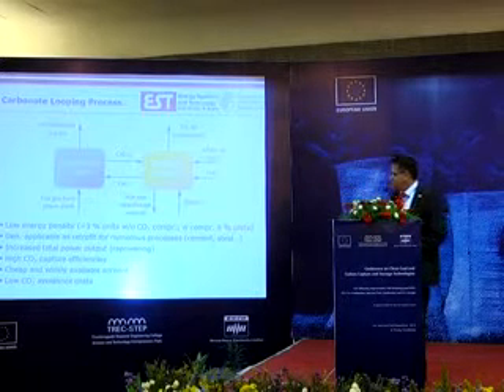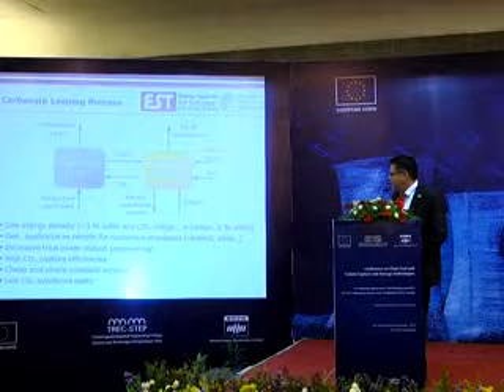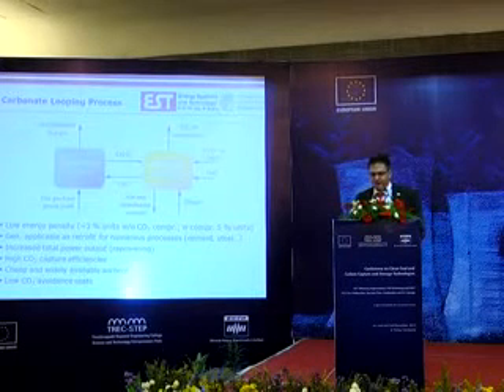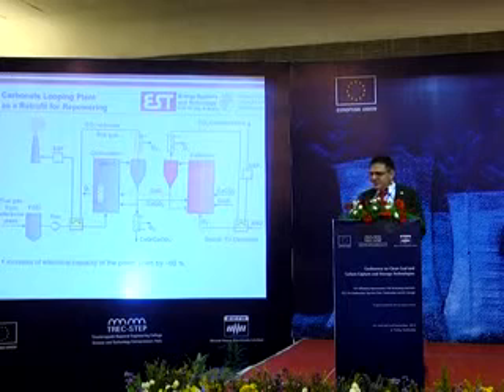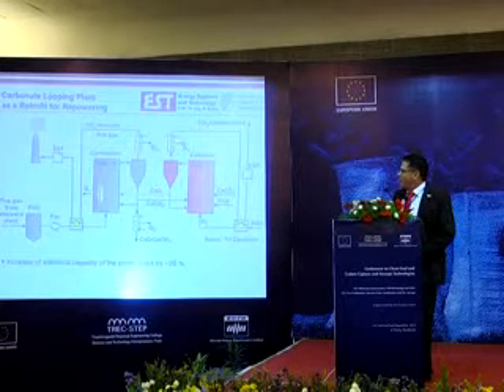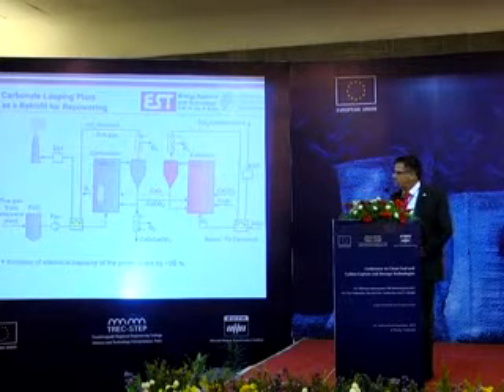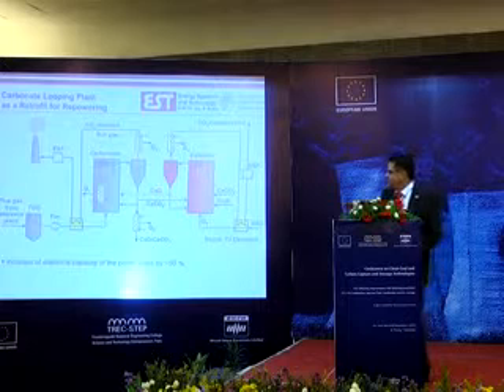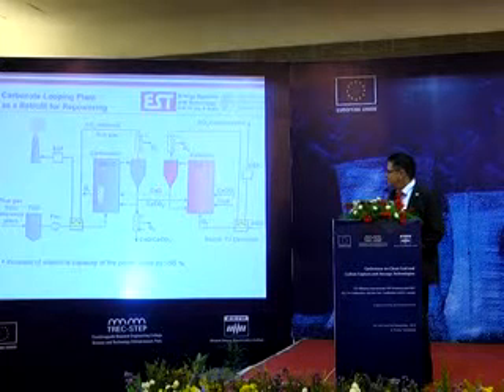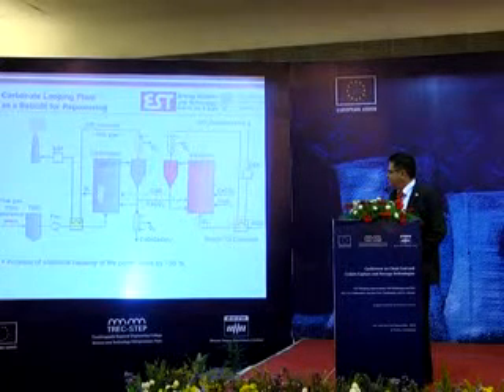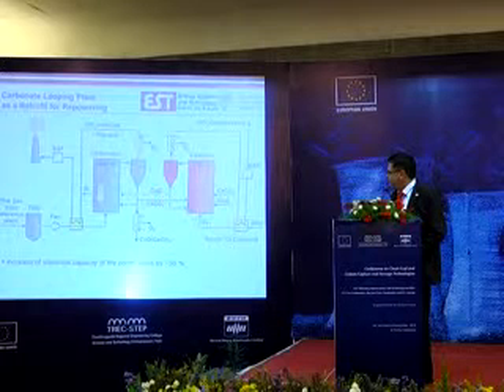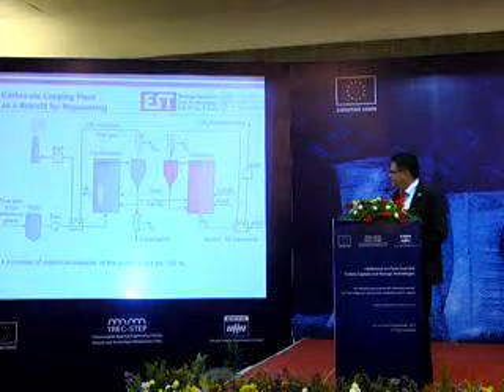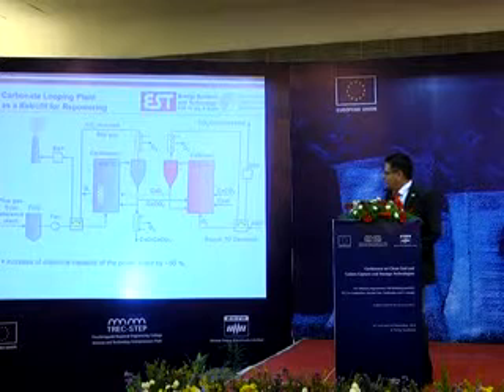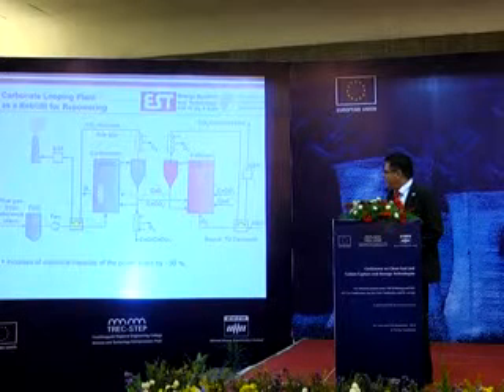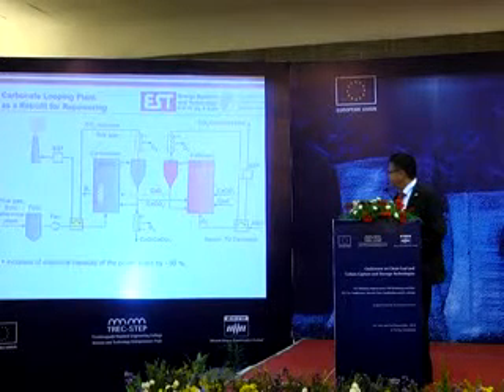And this process is associated with very low CO2 avoidance costs. So that's the setup of a carbon looping retrofit behind a power plant. That means the power plant is here in front. That's the end of the flue gas train. There's an FGD, flue gas desulfurization unit, ID fan, and then the carbon looping process starts.